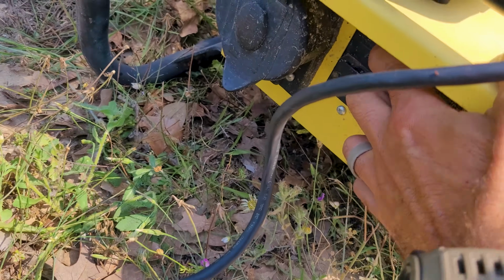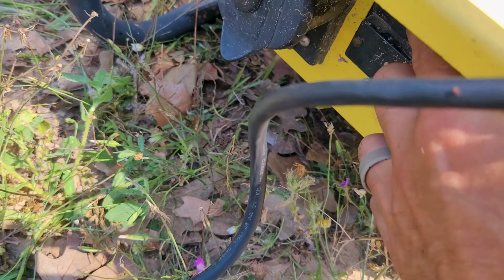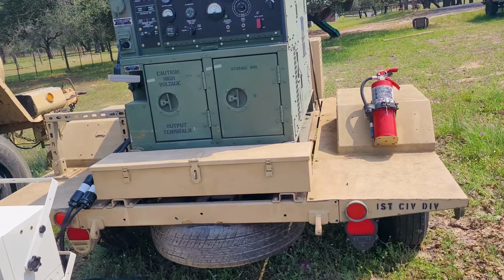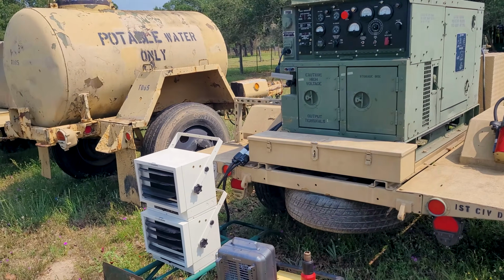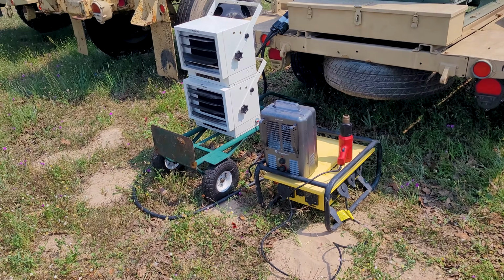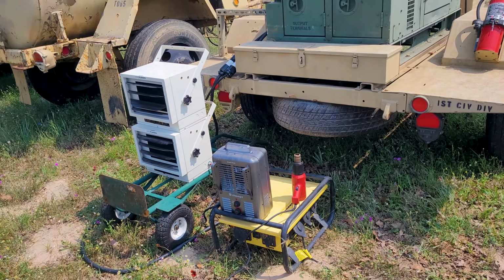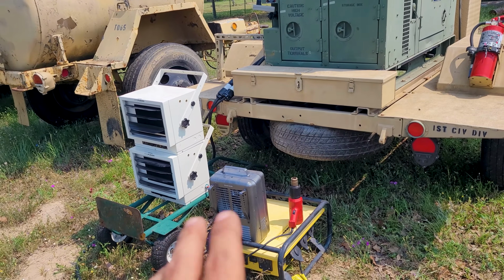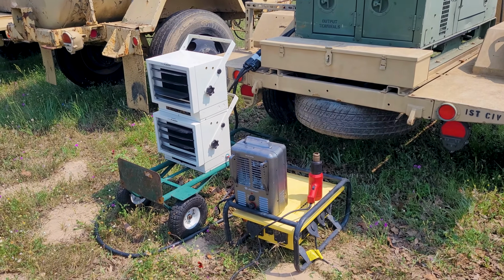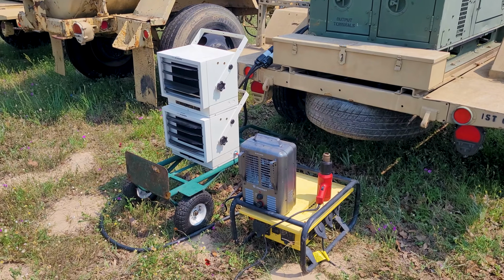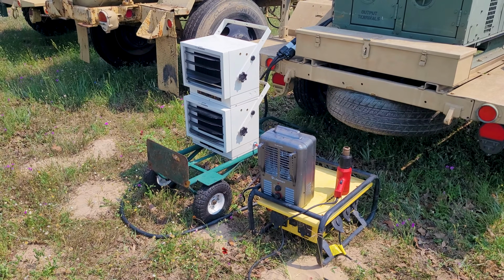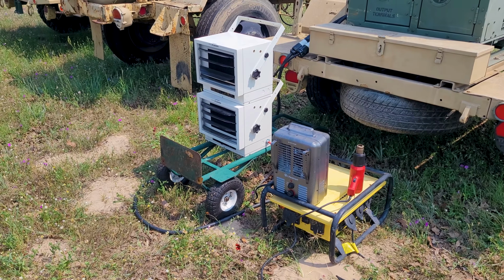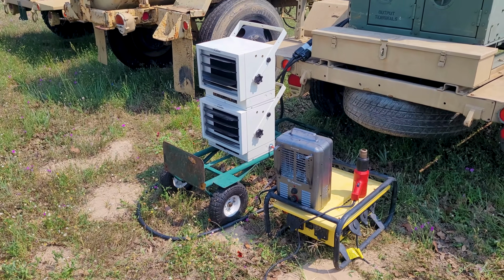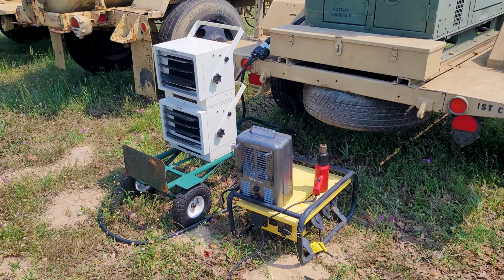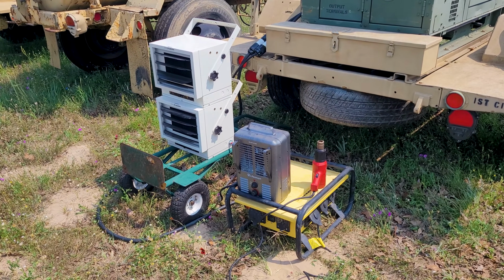Now, with my little distribution box here, every time I need to reset these little GFCIs that are on here. What I recommend next is don't just take your entire load bank and turn it all on, because what I have here, if I turn it all on together, is 12,900 watts of power at a 1 power factor. That's going to show different on the gauge, and that's something that confuses people because the gauge is a 0.8 power factor. As the time lapse is going, I'll explain that more in depth.